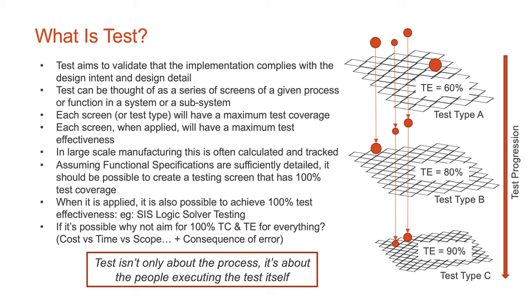You can measure that test effectiveness to an extent. In large-scale manufacturing, this is often calculated in detail and tracked through test processes. Assuming there's a functional specification that's sufficiently detailed, it should be possible to create a testing screen that has 100% test coverage. When it's applied, it's also possible to achieve 100% test effectiveness. A good example of that is a safety system with a safety logic solver, tested with every possible combination — 100% test coverage and 100% test effectiveness.